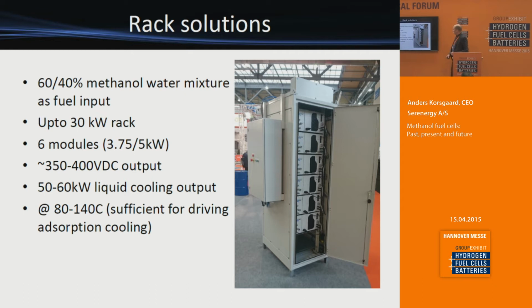Here's also one of the things we're exhibiting at the show. As you can see, it's a 19-inch rack with 6 modules in, totaling about 30 kilowatt peak load. It outputs about 350 to 400 volt DC, which is applicable as input for, for instance, a solar converter that can be on or off grid, operating in island or on-grid mode.